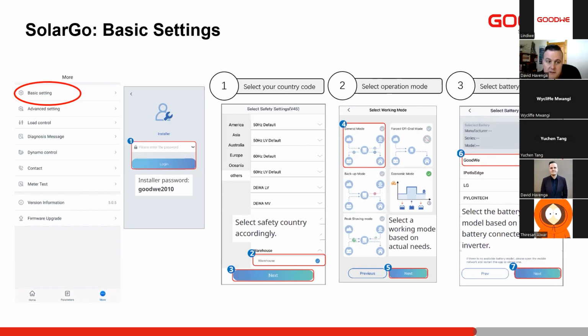First we'll select our safety country. This depends on which country we are in and what regulation we're working to. For this, we might select Africa, or we might select Germany. As an alternative, when we need a wider range input, we select 50 Hertz default. I don't think anywhere in Africa we should select the 50 Hertz LV default. This 50 Hertz LV default is for 120 volt grids. So please keep in mind that the LV default that you can see here on the screen, we should never use. Please never use that, because then the device will never connect to the grid.